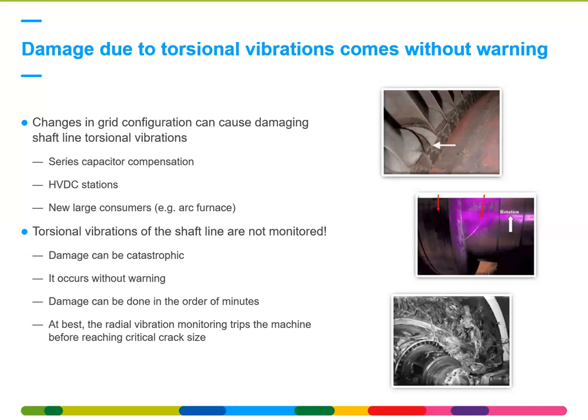The top figure is damage at the low pressure, typically the last stage blades of the low pressure steam turbine, which are known to be able to dynamically couple with the rotor torsional vibrations. So these are main examples of damage due to torsional vibrations, which have already occurred and which are still occurring and are considered to be more at risk in the future due to changes everywhere on the grid.